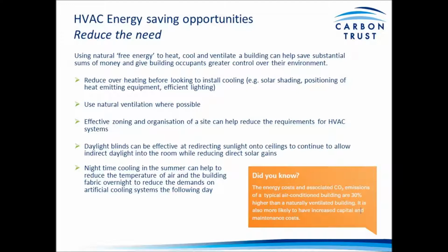And where you have varying heating or cooling demands across the site, make sure your system is flexible so that you only heat where required through effective zonal control. Daylight blinds can be effective at redirecting sunlight onto ceilings to continue to allow light into the building, but without having excessive heat gain, which again requires cooling. Or again, you can look at night cooling as a means of allowing cool air into the building overnight to lower the temperature at the start of the day. This is particularly effective in office buildings, just to reduce the cooling demand once the office building gets started.